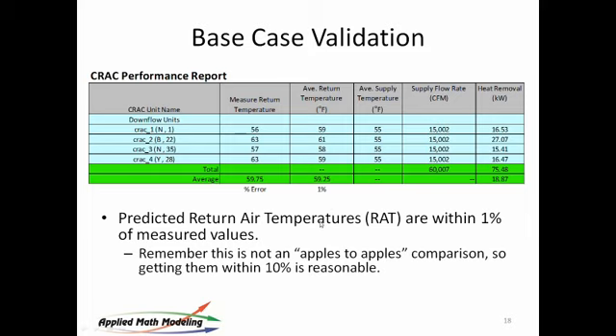Now, we want to point out that this is not quite an apples-to-apples comparison, because the return temperature is not a constant either. If you look at the return temperature, there's a sensor somewhere that is measuring the temp in the real world, at a given point on the surface area of the return plenum, usually at the top of the CRAC unit. But that's only one point. There's actually many points. Remember that temperature is not uniform across the entire return surface of the CRAC unit. And as a result, they're just picking one point.